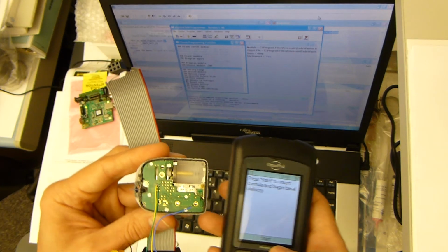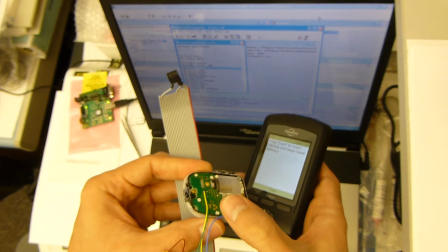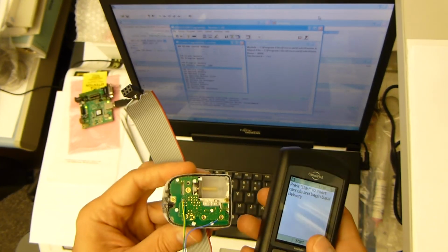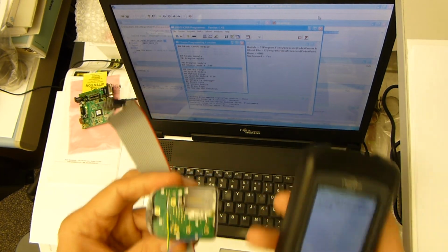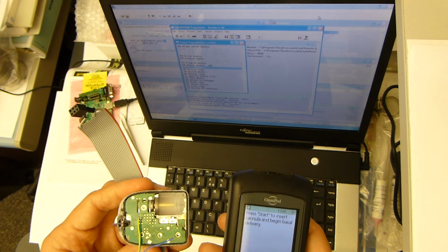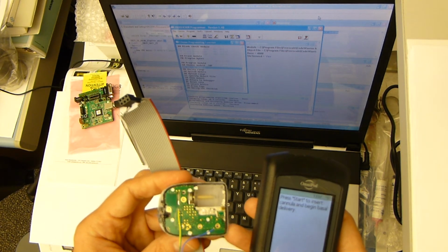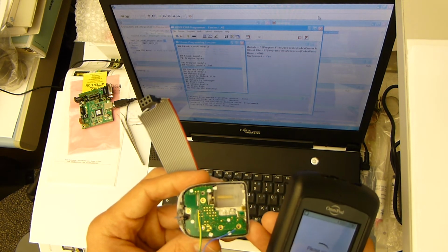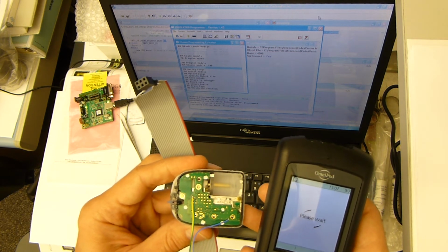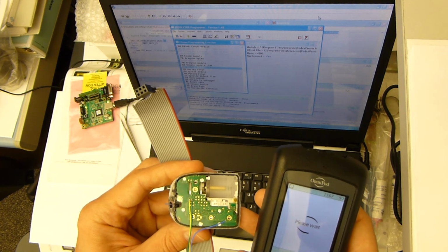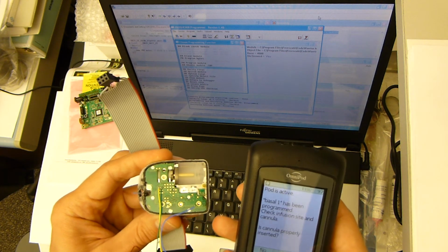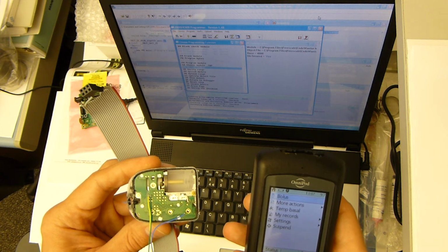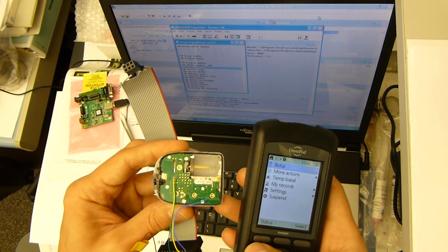Now the pod is ready for the cannula insertion, but because it's a used pod, we cannot restart the cannula insertion process because the mechanical mechanism inside the pod is one-time use. So we just press the start button so that the software inside the pod thinks that the mechanical part is working. So a few more turns of the gears and the pod should be ready for the normal operation. So we say everything is okay.